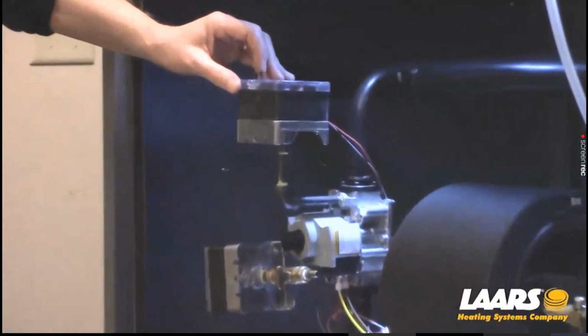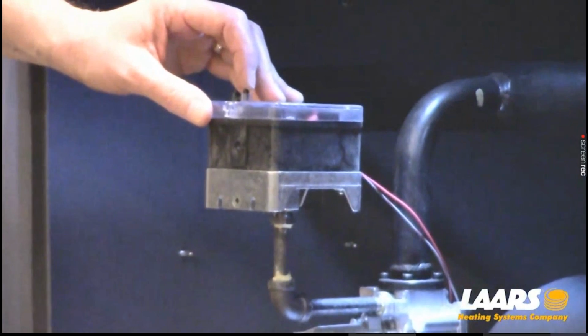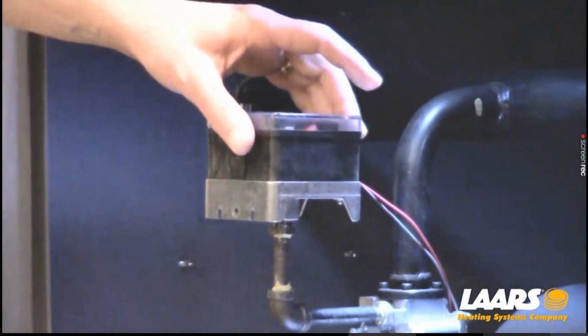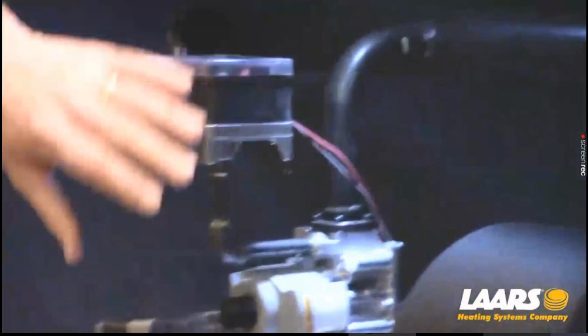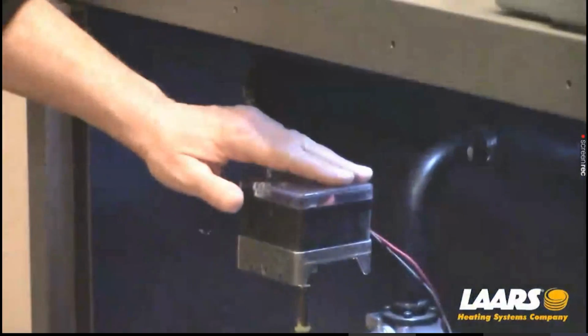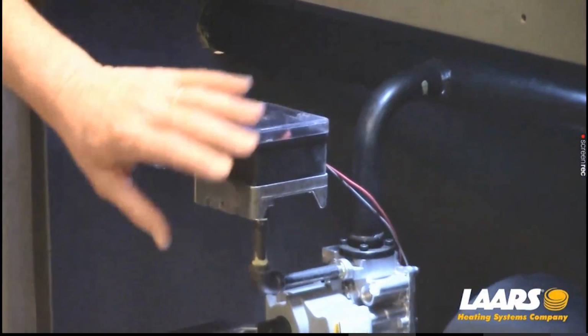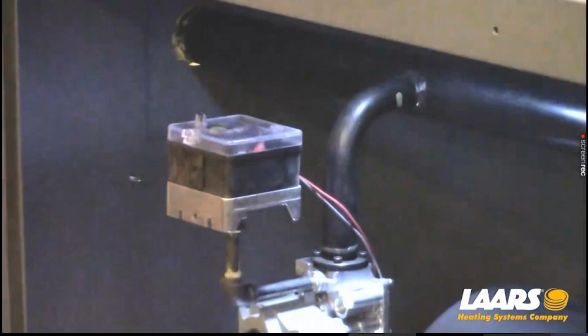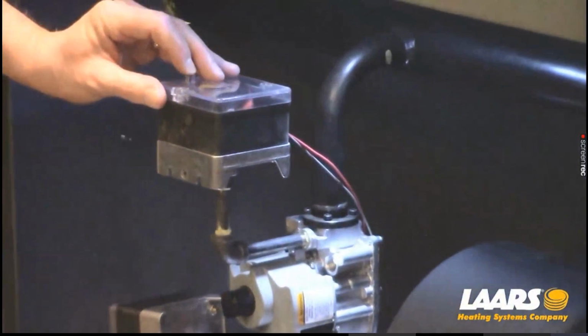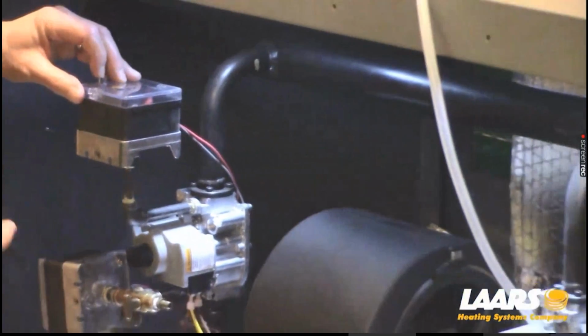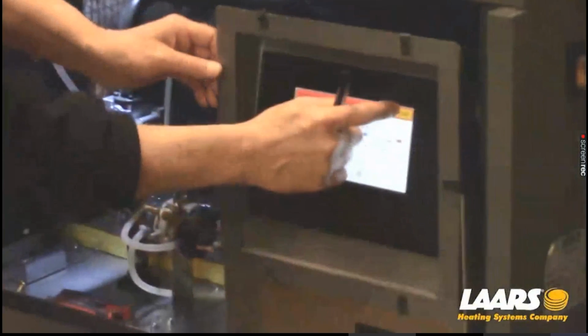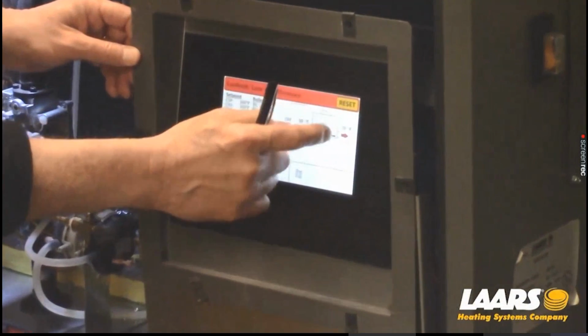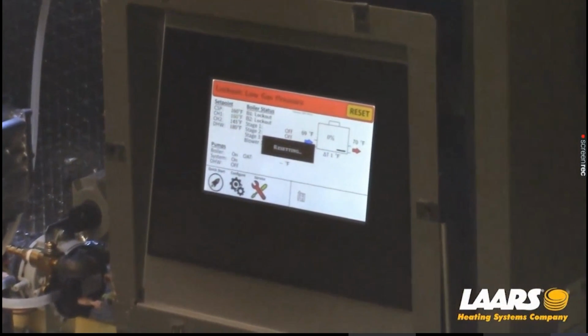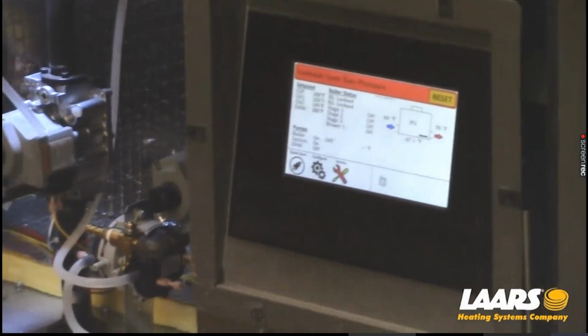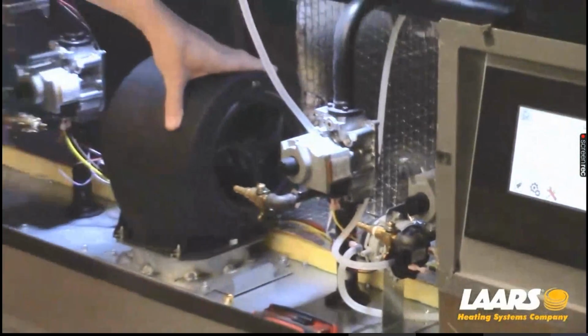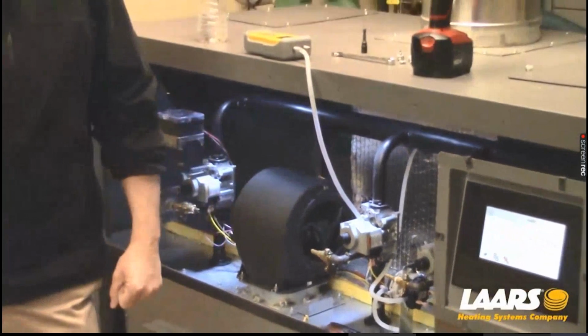When we leave the factory, we test fire each boiler, but we obviously remove gas. If you're a CSD1 that has high and low gas pressure switches, this will be tripped. If you're non-CSD1, you will not have these controls. I'm going to reset it here, come over to my touch screen and reset it here. Now I also want to mention, if this blower is running, I would not be able to reset it. I have to wait till the blower times out.